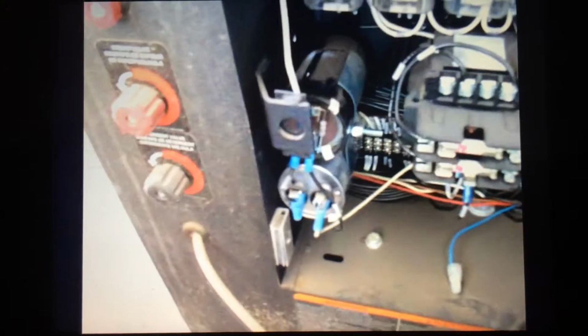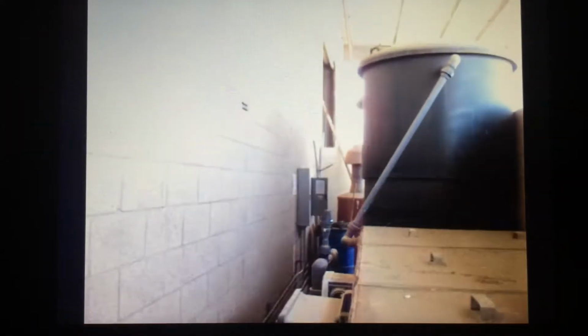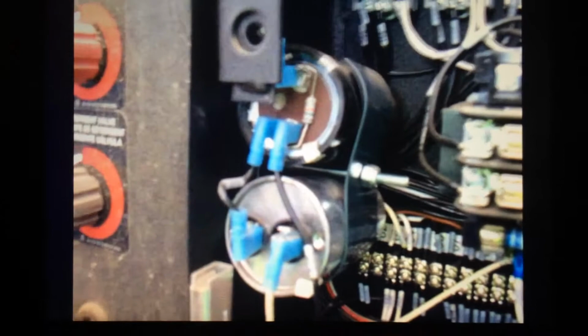Now, if you've got a bad start capacitor, a capacitor holds an electrical charge, kind of helps get the motor started up to speed. It stores an electric charge. We can check to make sure the capacitors are good first. In this case, what we do is we shut the breaker off to the machine. We follow the electrical conduit along the wall, and we find the breaker, and we make sure after we shut the breaker off, then we verify at the top of the contactor whether or not there's power. That's very important. As long as we don't have power, then we can go ahead and come down to the capacitors. These capacitors right here, the start capacitor and the run capacitor, are right next to each other.